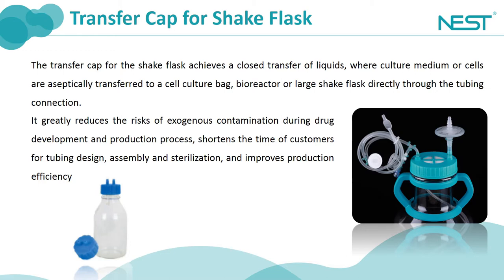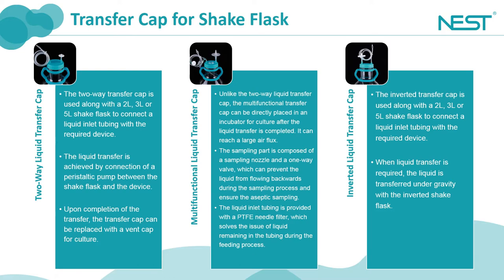What's the function of the liquid transfer caps? If the volume of cell subculture is very high, the company will prepare a lot of culture medium and store it in a large reservoir bag for centralized distribution. Some clients use a blue cover bottle — they first transfer the medium into it via tubing, then pour it into the shake flask in a super clean bench. This whole process is very cumbersome and can easily cause contamination. With our liquid transfer caps, clients only need to screw the transfer cap onto the flask, connect the tubing to the reservoir bag, and start liquid transfer with a peristaltic pump.